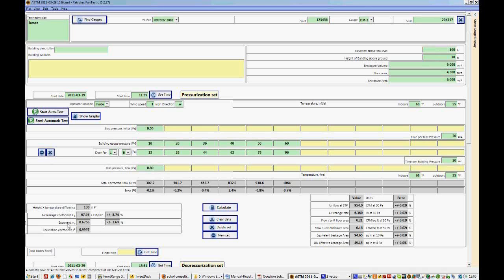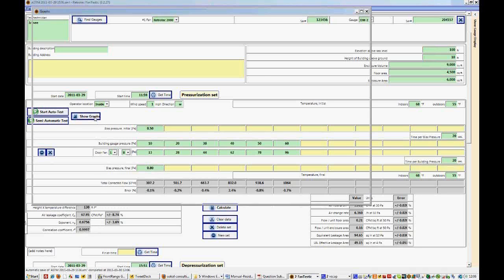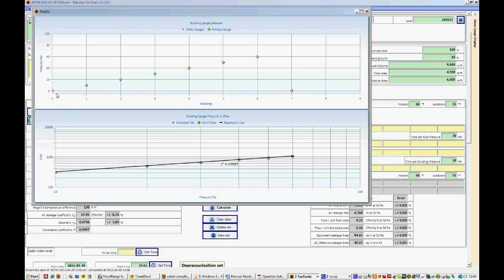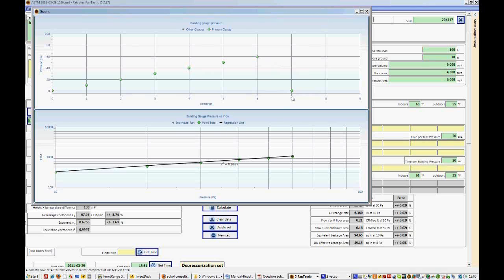Now these things make up the equation of the line that we can see in this graph. So the first graph on the top shows us the pressures that were taken over however many readings. The first reading that we took was an initial bias pressure and that was just above zero. And then we have our six building pressures that we took, up to 60 pascals. And then we have our final bias pressure.